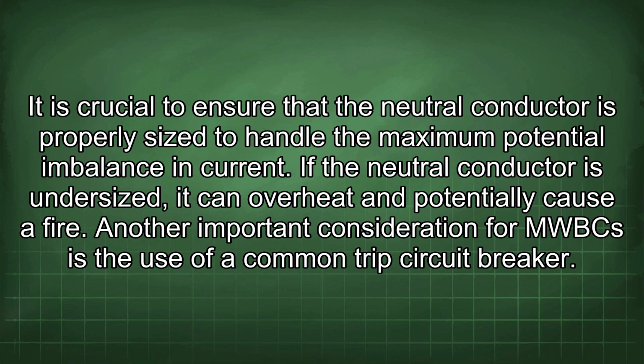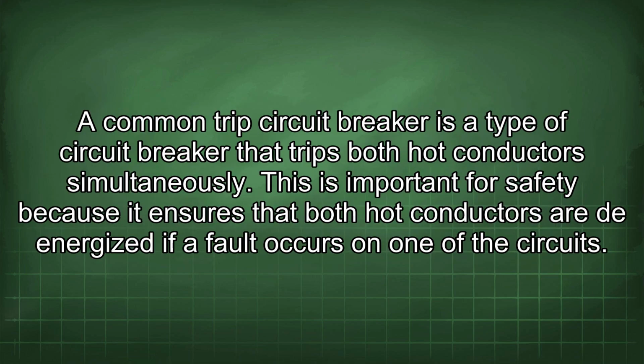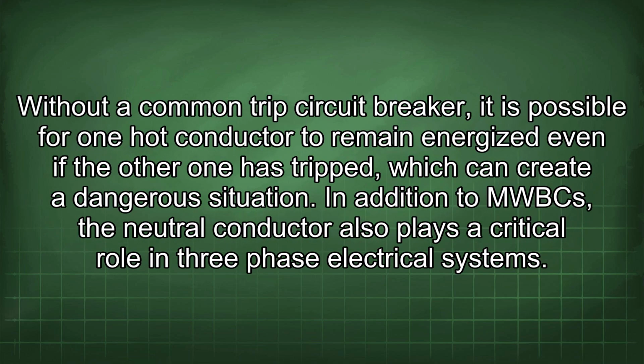Another important consideration for MWBCs is the use of a common trip circuit breaker. A common trip circuit breaker is a type of circuit breaker that trips both hot conductors simultaneously. This is important for safety because it ensures that both hot conductors are de-energized if a fault occurs on one of the circuits. Without a common trip circuit breaker, it is possible for one hot conductor to remain energized even if the other one has tripped, which can create a dangerous situation.